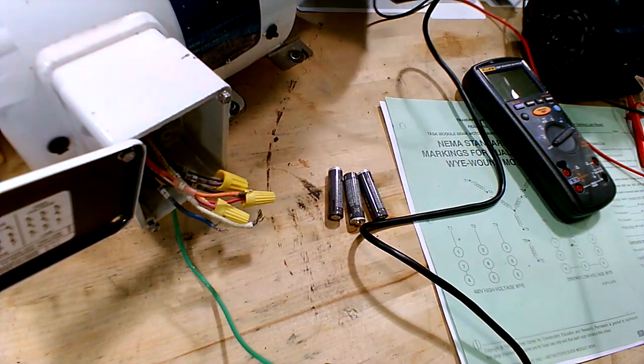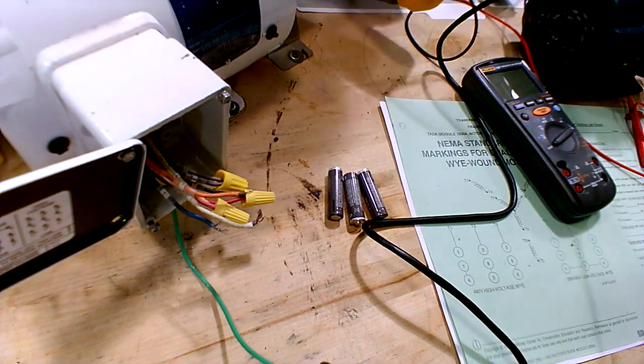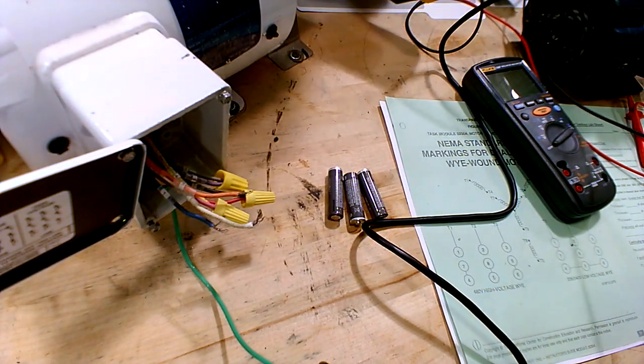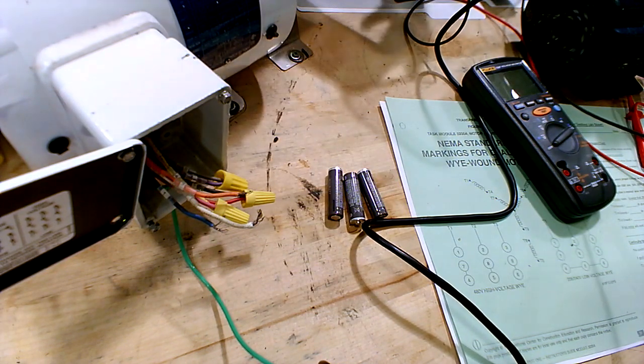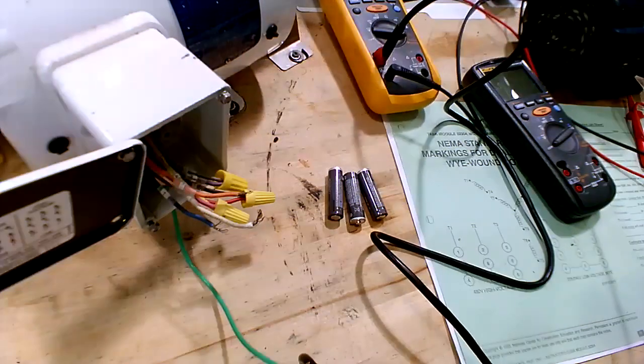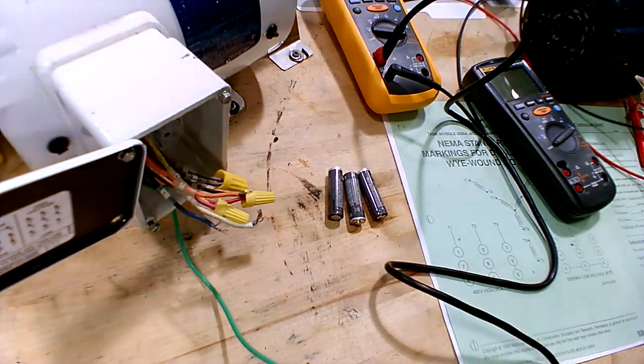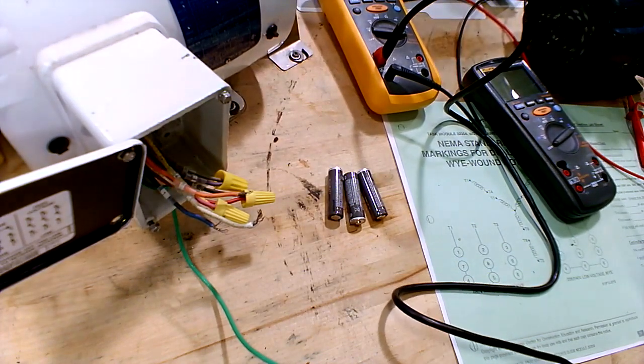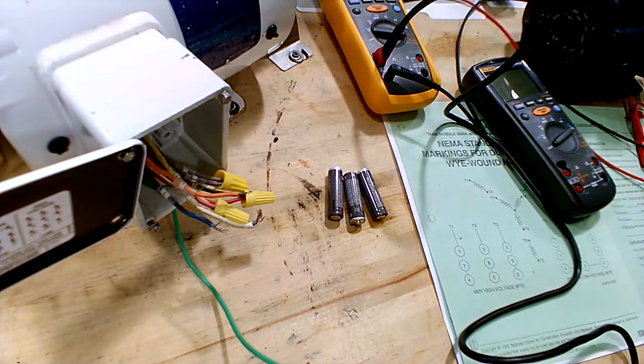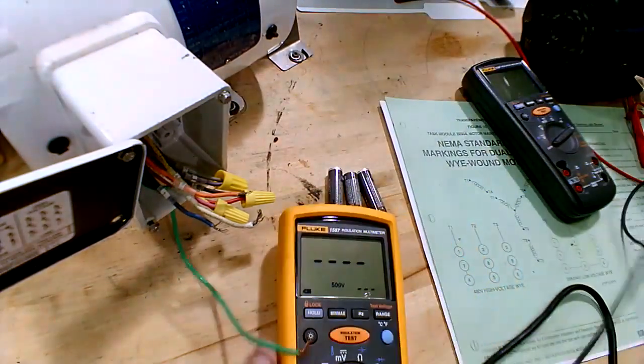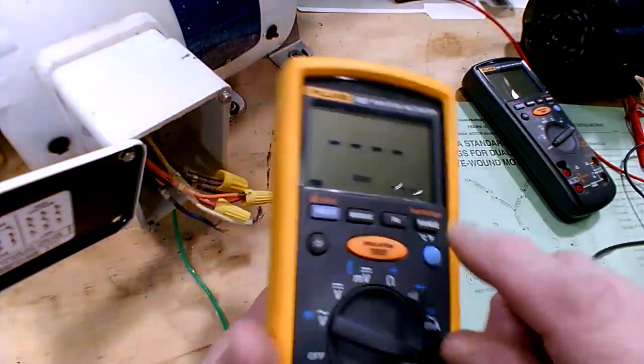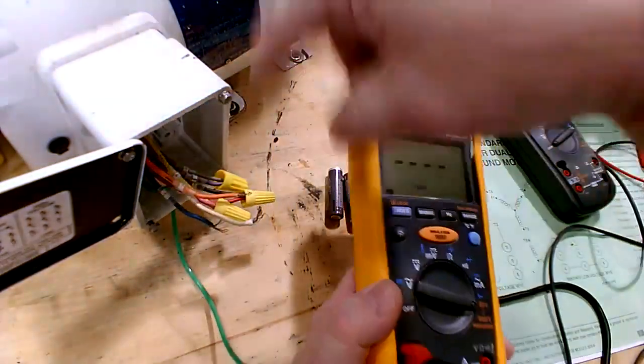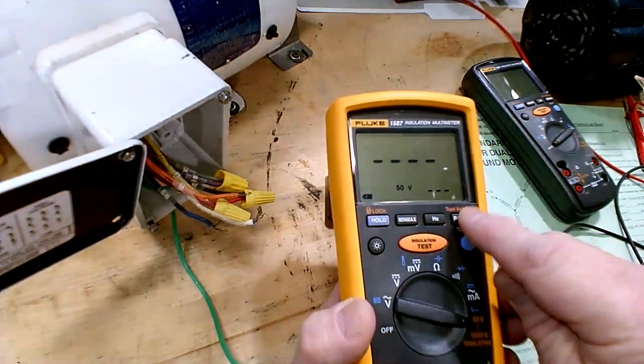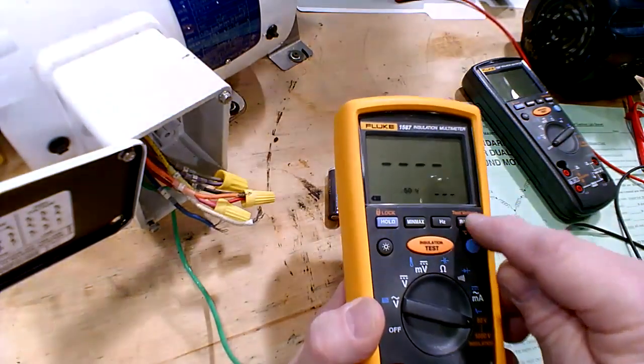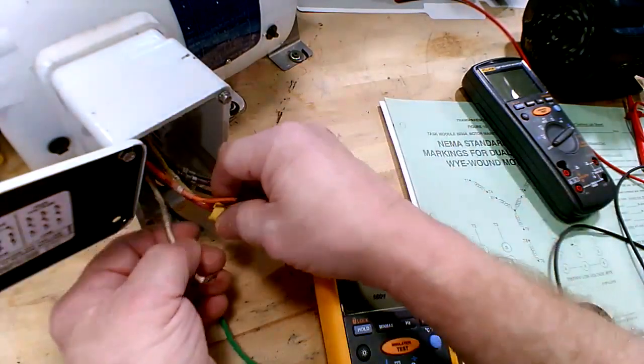No. So look, for the range, we're going to select the 500 volt range. It'll actually put 500 volts on the motor and then test it. So we get right around here. Stand right here. So this thing's going to produce 500 volts. The range is adjustable. If you wired that motor for 480, you go to 500 on this. If you wired it for 240, then you're going to set that setting down lower, around 250. Okay, we're going to go to 500, and you got this set for high voltage.